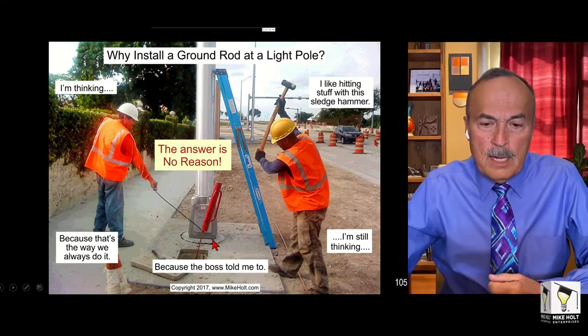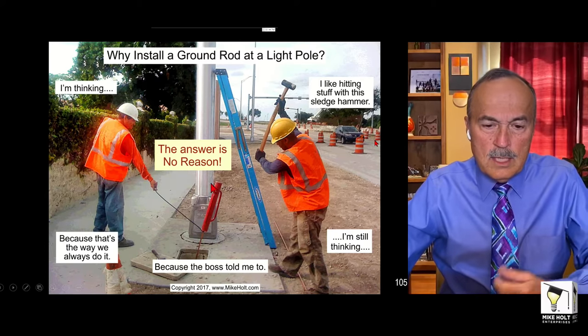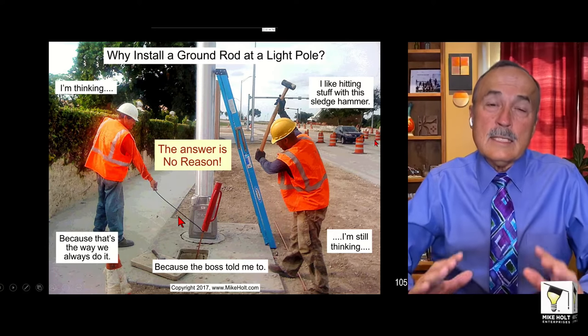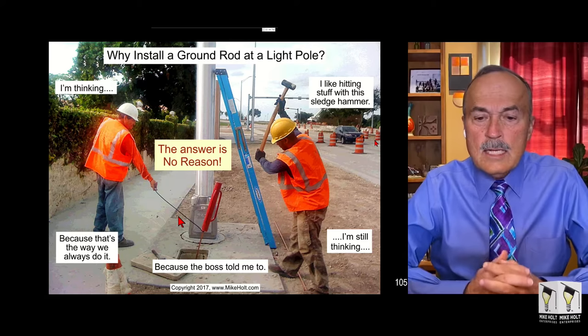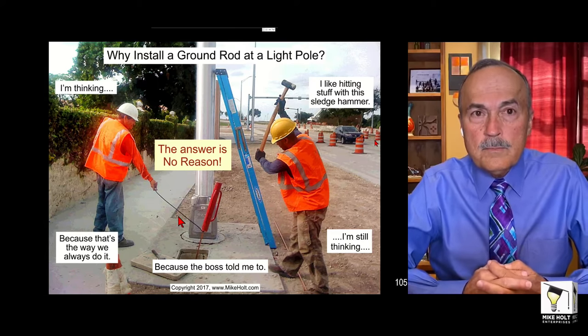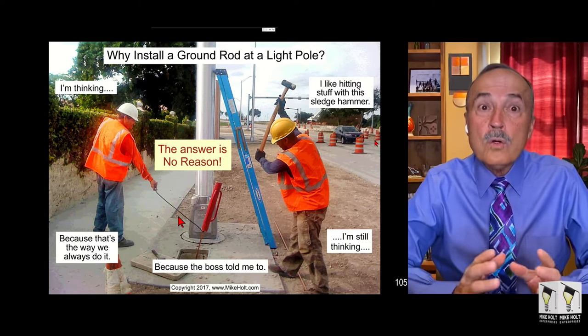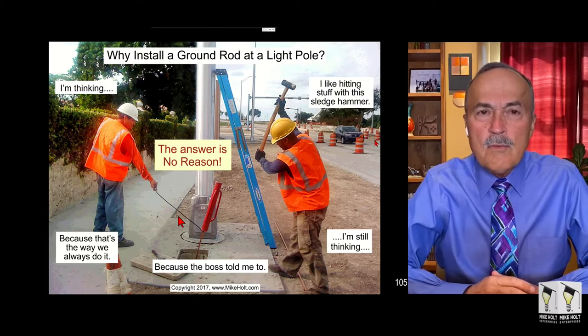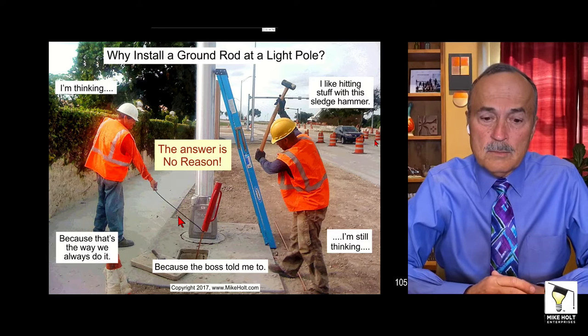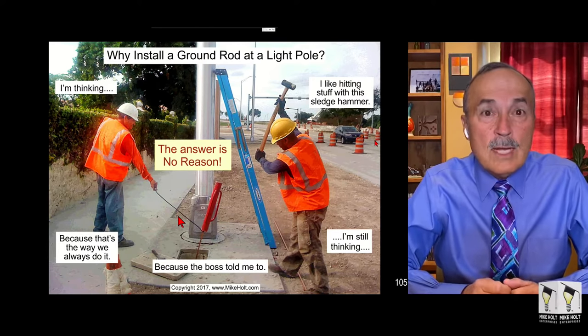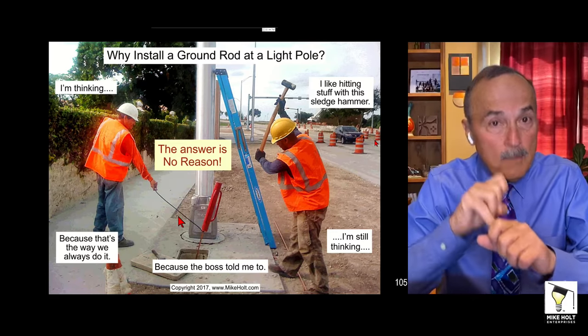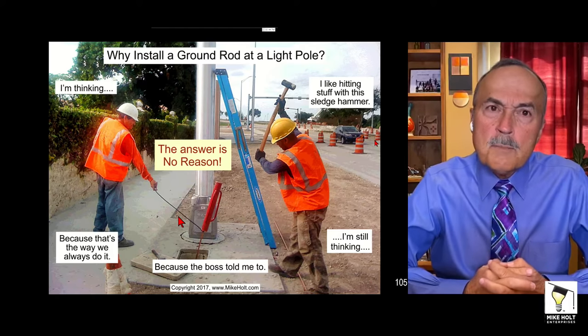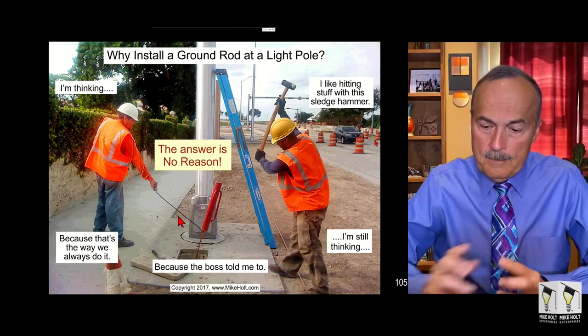This is in Miami - I was driving by and saw guys driving ground rods with a sledgehammer and ground rod driver. This is actually in Coral Gables in South Florida. Coral Gables is a coral rock area, so driving a ground rod there is pretty difficult, if not almost impossible. Why are they driving ground rods? Because the spec shows it, or an inspector might come out and say they don't see a ground rod at the pole.